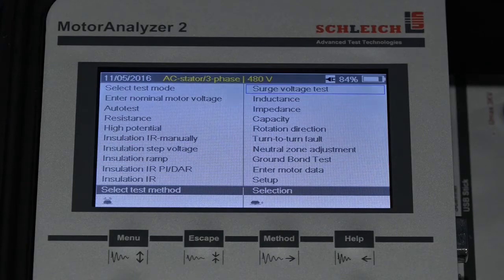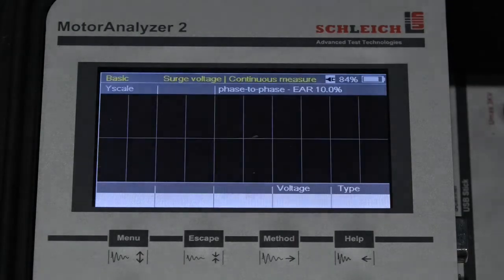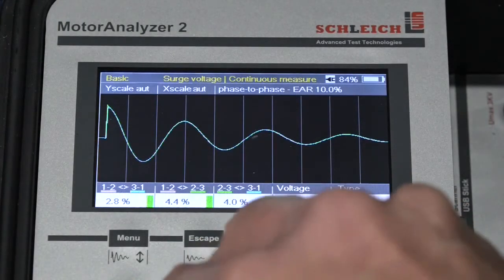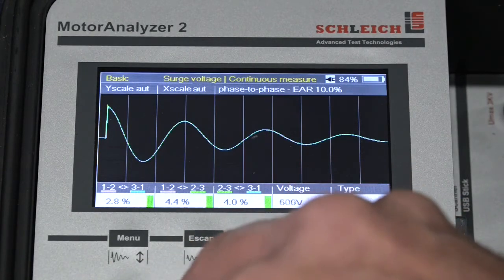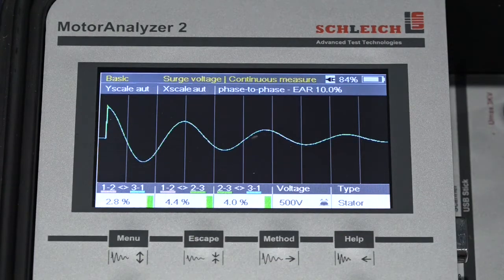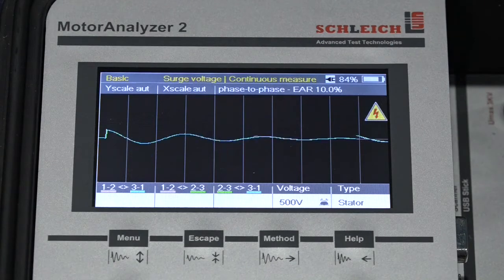So in a motor shop setting, often we don't want to run a full automatic test. We just want to run a surge test after we installed some coils, and just run, say, a DC high pot test. We don't want to do a fully automatic test. To do that, I'll use the whiz wheel to select, say, the surge test. And we've got control of the knob voltage here. So I'm going to take the voltage down to 500 volts and press the test button. So it's applied 3 pulses to leads 1, 2, and 3, and we're getting our 3 different waveforms and calculating the phase-to-phase error area ratios.